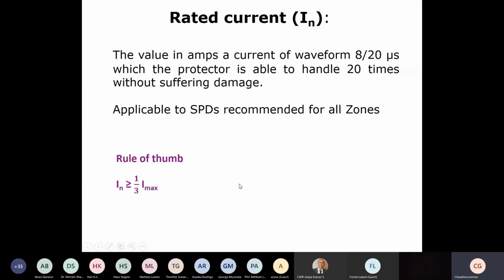Every SPD should not only be tested for the IIMP or IMAX. Apart from that, you have to apply the 8 by 20 microsecond waveform 20 times and say what is the maximum current that the SPD can withstand. This shows how robust the SPD is for multiple lightning currents. Again, there's a rule of thumb that the rated current should be greater than about 1/3 the IMAX. And then we go to voltage protection level.